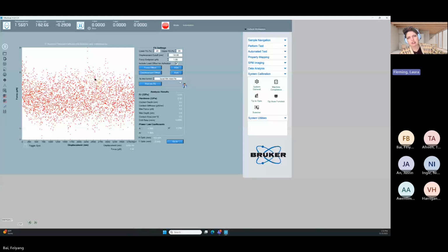If you don't define the tallest sample, you run the risk of crashing the transducer against a tall sample and breaking the piezo scanner, and at worst, the transducer. That's how I see them get damaged most often. Now, I did just say that there is an emergency stop. That's only on the actual probe itself. The transducer housing doesn't have any sensors. So it's only if we apply force to the probe that the emergency stop will occur. So, third question, are our samples defined? And the answer is no.